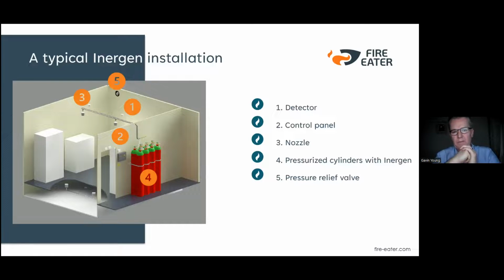You have a control panel, your detection, and your nozzles at the end of your pipe work that give a uniform concentration. So they are calibrated. This is done through software that we have. It designs the size of the pipe work and the calibration of the nozzles. The pressure in the cylinders for our system is between 200 and 300 bar, depending on the risk.